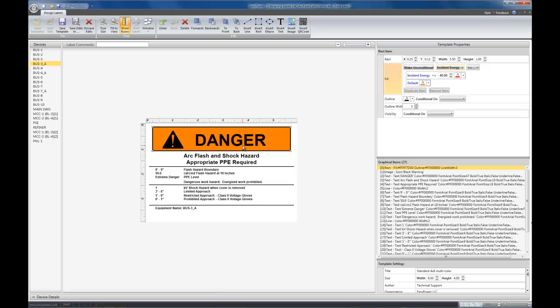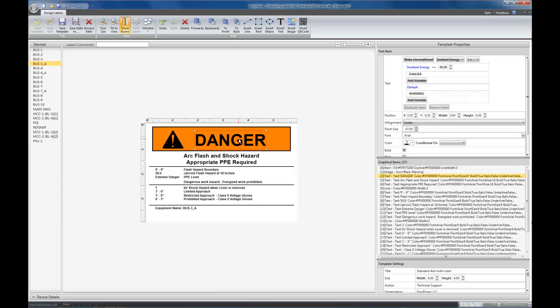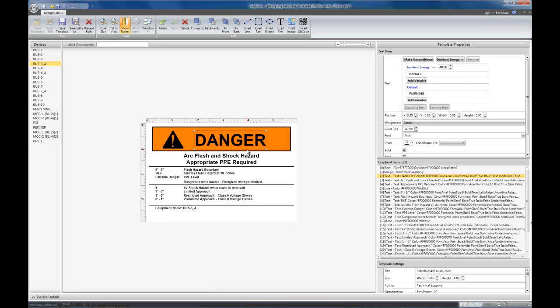So the second type of item that you can have be conditional within a graphical item is the text itself, the text content. There's two graphical items that have text content: one is the actual text item, and the other one is the QR code. Both allow the text content to be conditional. For example, in this case, we're already making the text on the title block either say danger or warning. It's danger, again, if incident energy is greater than 40, and it's warning otherwise.